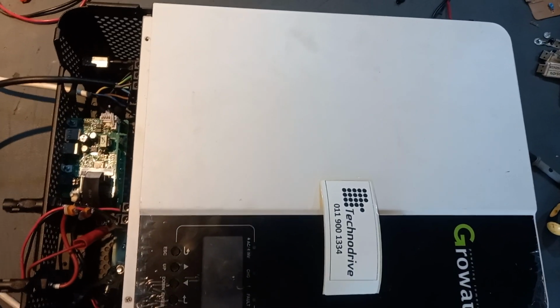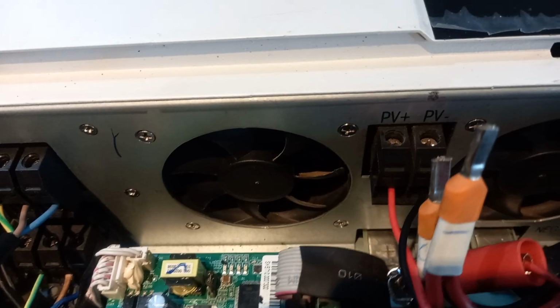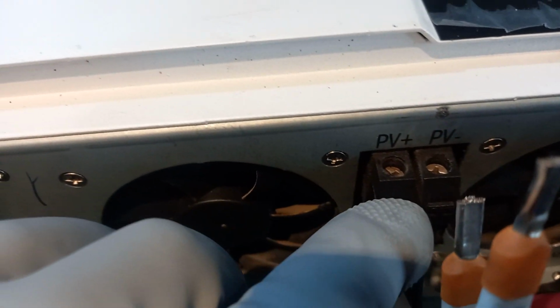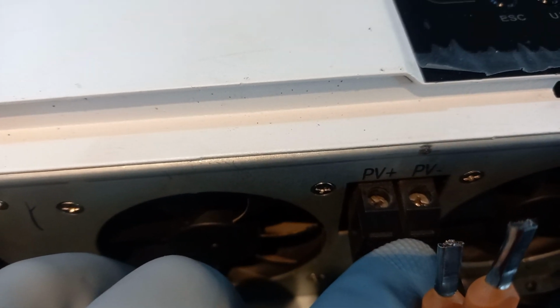Okay, there is the full view of your inverter. You can see this is the same inverter that you brought. Okay, all right, let me show you. Before we test, let me show you something here. You see here on the PV, there's an arc there. So this tells you that when they were working on the inverter, the power was still on.